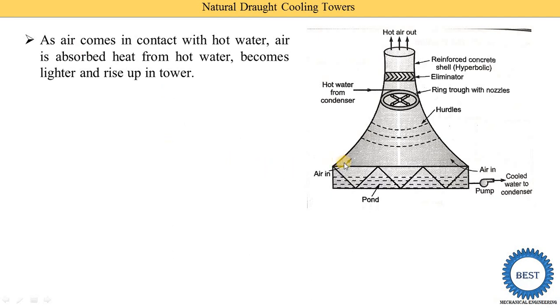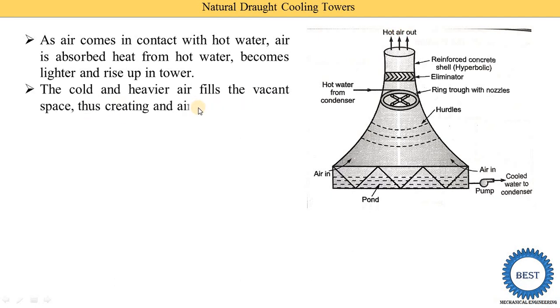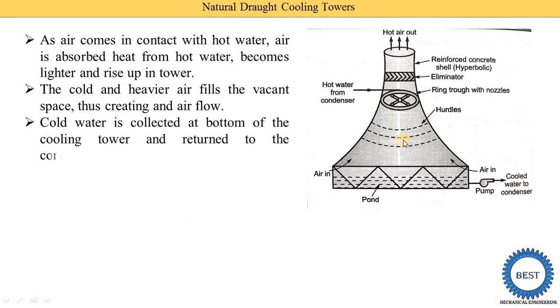Air enters from the bottom, absorbs heat energy from the water, and when it absorbs heat its density reduces — it becomes lighter air and moves upward. It is then discharged to the atmosphere from the top of the tower. The cold and heavier outside air fills the vacant space, creating continuous air flow. When this air moves upward, space is created and new air from the atmosphere takes its place — this way the continuous natural flow of air is maintained.